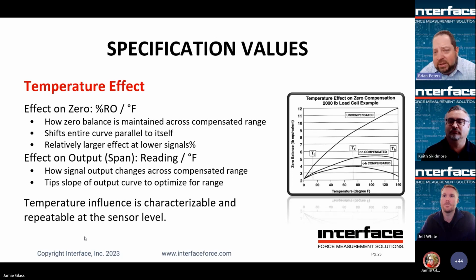Load cells certainly can be used outside the compensated range. It's not going to suddenly fall off a cliff in terms of what's going to happen to the signal or the zero balance, but you can imagine that's going to start to deviate outside, of course, the specified range as soon as you get out of that stated value there.